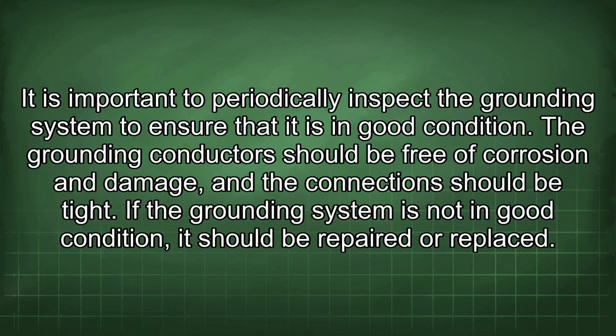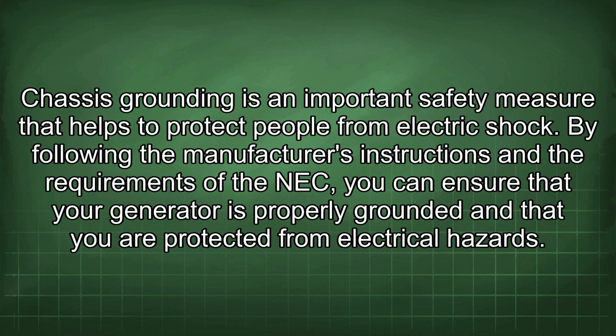It is important to periodically inspect the grounding system to ensure that it is in good condition. The grounding conductor should be free of corrosion and damage, and the connections should be tight. If the grounding system is not in good condition, it should be repaired or replaced. Chassis grounding is an important safety measure that helps to protect people from electric shock. By following the manufacturer's instructions and the requirements of the NEC, you can ensure that your generator is properly grounded and that you are protected from electrical hazards.